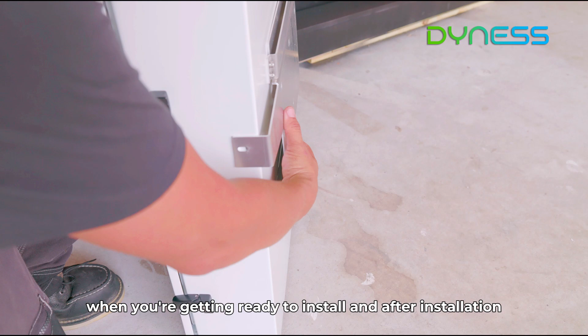First thing you want to do is look at the back of the smart controller. There's a safety bolt that you need to put in place and you're getting ready to install and after installation. Backing slides into place after installation of the wall. What I like to do is start off with the center bolt to verify that you have balance on everything. So when installing this, you do want to use all 4 anchor points for this installation. Very critical. So just in case it doesn't fall off the wall and void your warranty through Dyness.